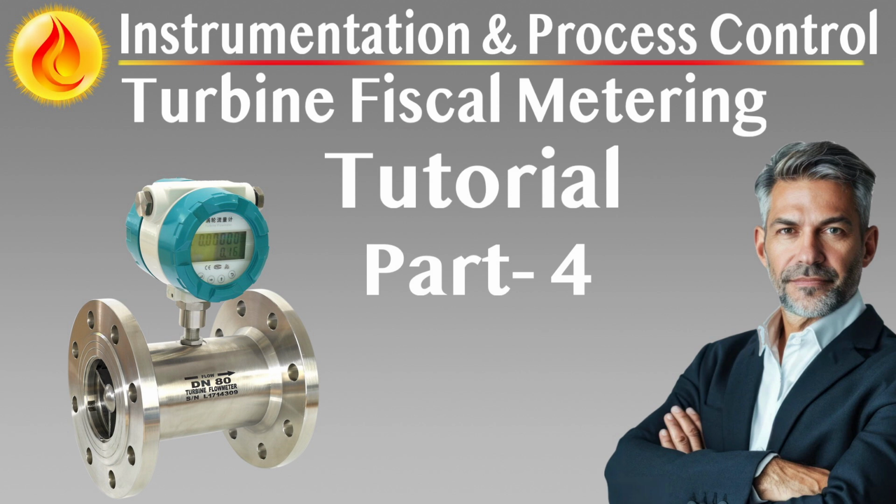The prover must include provisions for external recalibration using a master prover or calibrated master meter. This includes flanged ports or bypass lines for loop-in verification, ensuring the long-term validity of the prover's own reference volume. Internal surfaces of the prover must be coated with a durable, non-porous lining to ensure a smooth, consistent bore over time. The coating must withstand the process fluid, pressure cycles, and potential decompression effects. All surface preparation, application, and repair procedures must be documented and traceable.